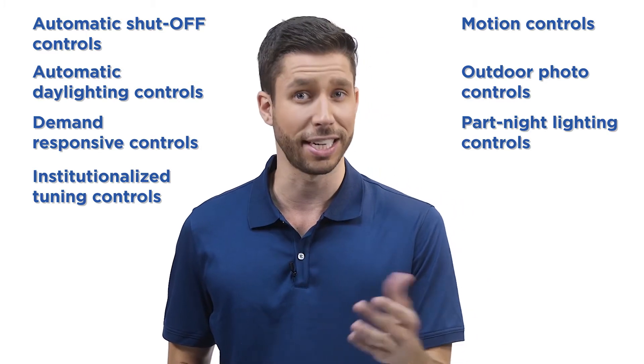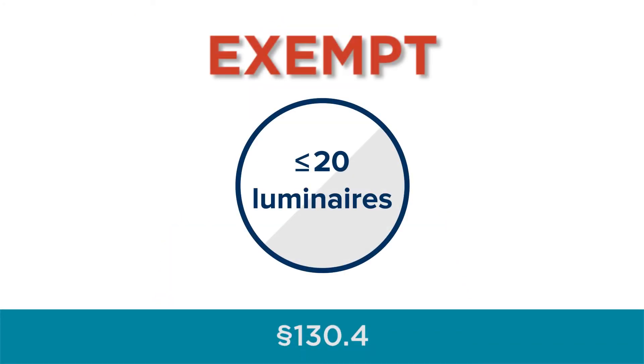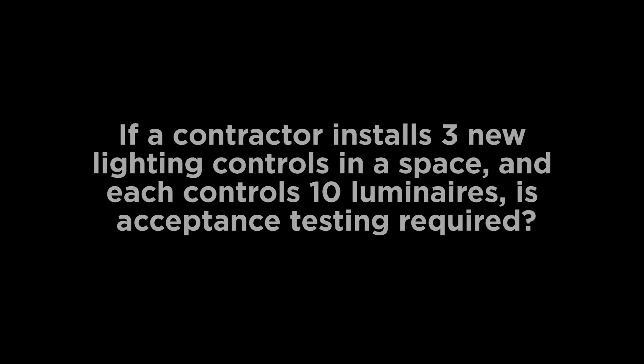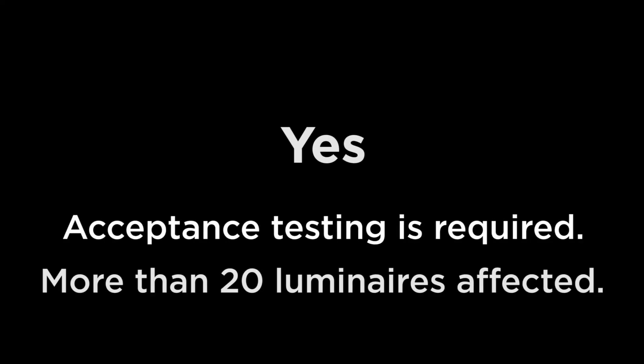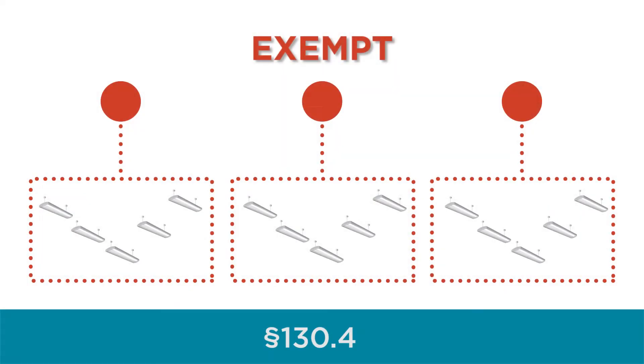These controls must comply with acceptance testing requirements per section 130.4. A new exception for lighting alterations states that when a lighting alteration project adds lighting controls to control 20 or fewer luminaires for the entire project, the project is exempt from acceptance testing. For example, in addition to a fluorescent to LED conversion, a building owner asks for occupancy control. The contractor installs three new occupancy sensors in the space and each controls 10 luminaires — a total of 30 luminaires. Since the total exceeds 20, acceptance testing is required. However, if each sensor only controlled five luminaires, bringing the total down to 15, the project would be exempt from acceptance testing requirements contained in section 130.4.